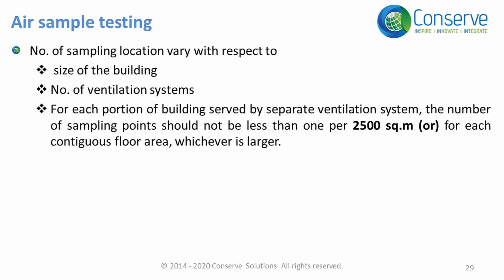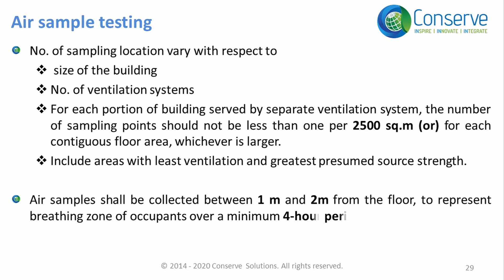The air sampling shall be collected between 1 meter and 2 meters from the floor to represent the breathing zone of occupants over a minimum 4-hour period. If the concentration at a sampling point exceeds the limit, the respective places have to undergo a separate flush out with outside air and the test conducted again. This has to be repeated until all requirements have been met. When retesting non-compliant building areas, take samples from the same location as in the first test.